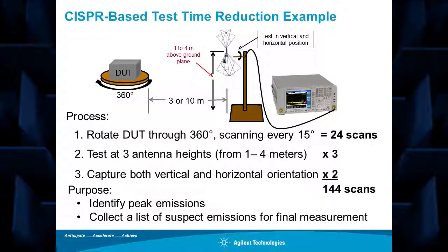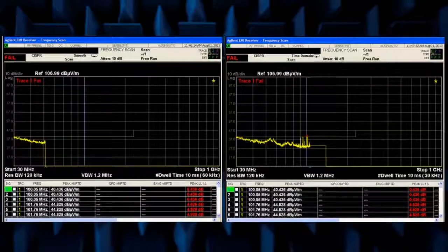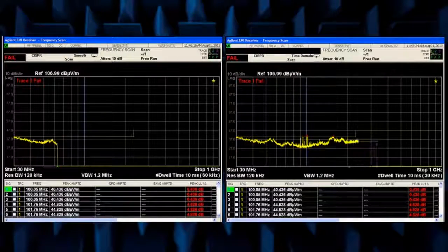To find the point of maximum radiation, hundreds of scans must be made for different combinations of turntable angles, antenna heights, and antenna orientation. The CISPR dwell time requirement makes scanning time consuming.